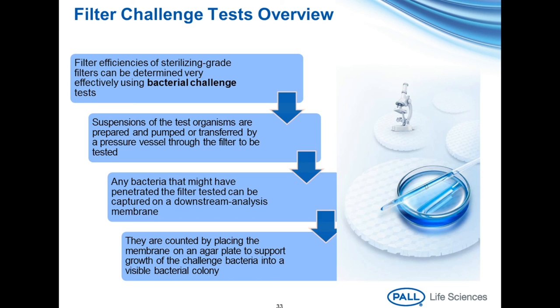Filter efficiencies are evaluated using a bacterial challenge test. Suspensions of test bacteria are pumped or pushed through a test filter, immediately followed by passage through a secondary analysis filter, which serves to capture any bacteria that managed to pass through the test filter. The analysis filter is then directly plated on culture media. In this way, the entire effluent is analyzed for the presence of bacteria, and passage of even a single bacterium—measured as colony-forming units—would indicate a failure of that bacterial challenge test.